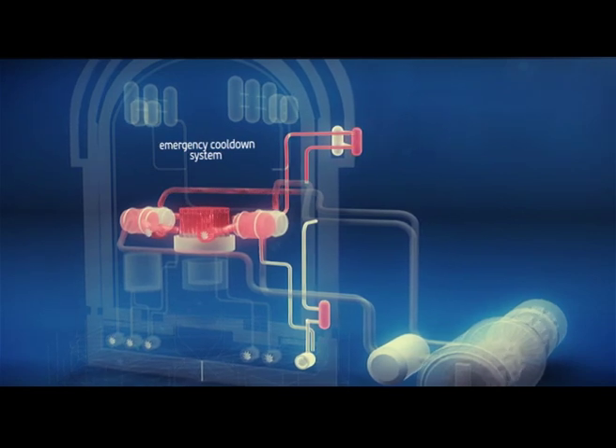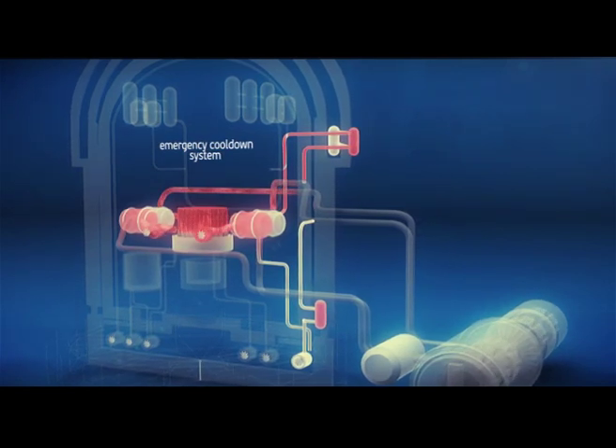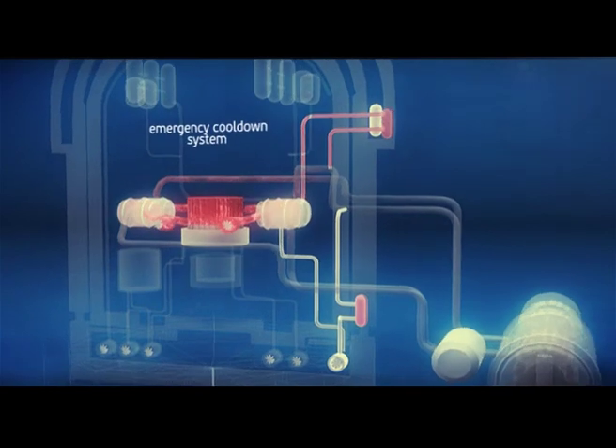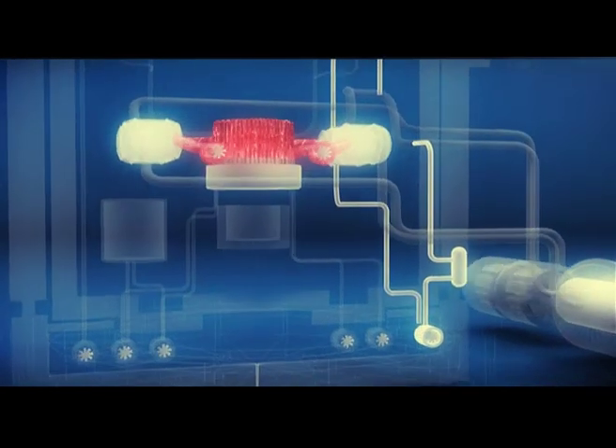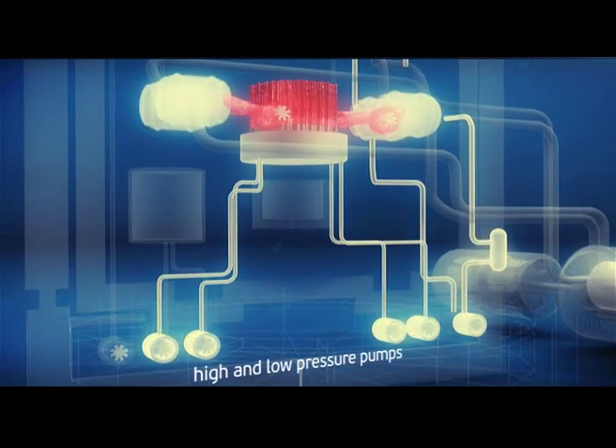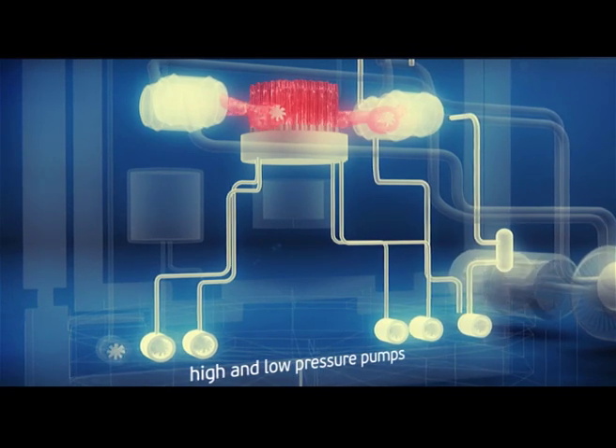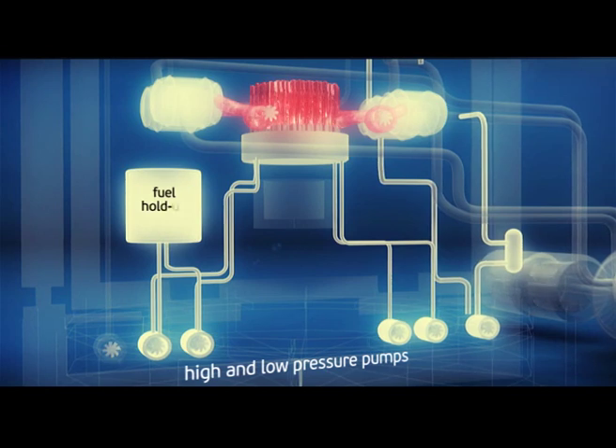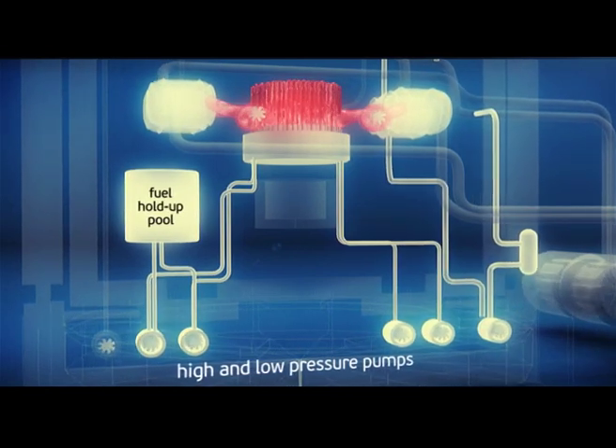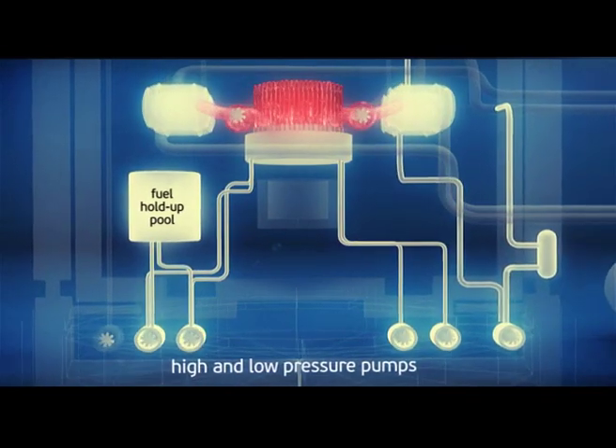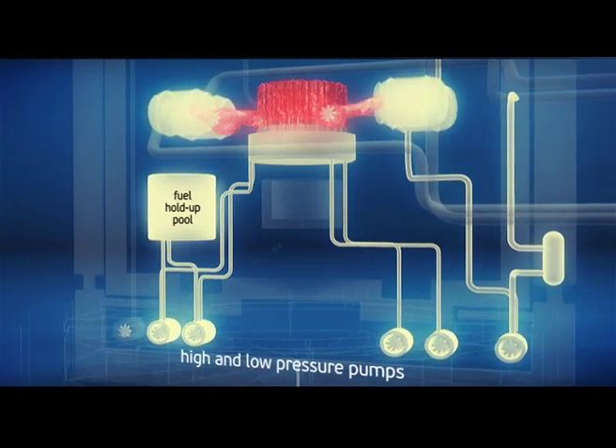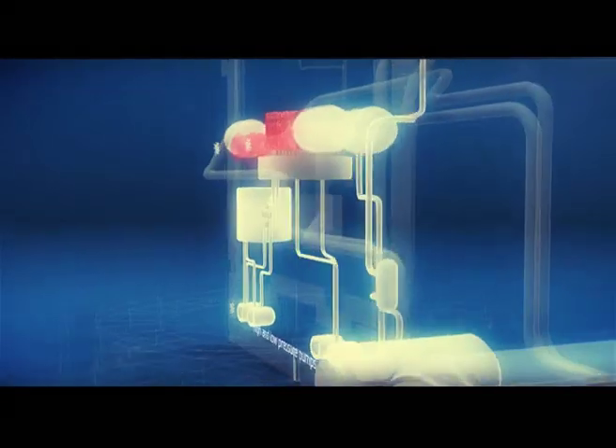In case the primary circuit is damaged, high and low pressure pumps are actuated to ensure continuous water supply to cool the reactor. They supply water from the spent fuel holdup pond located within the containment and from the containment sump. If the leak is small and high pressure is maintained in the circuit, high pressure pumps operate. If the leak is large, for instance in case of a pipeline break, and pressure is dropping, low pressure pumps are engaged.